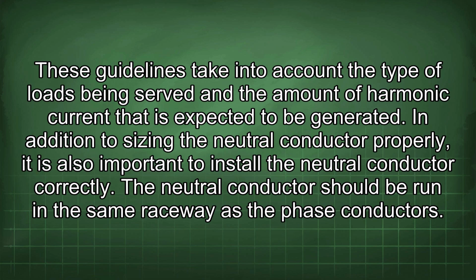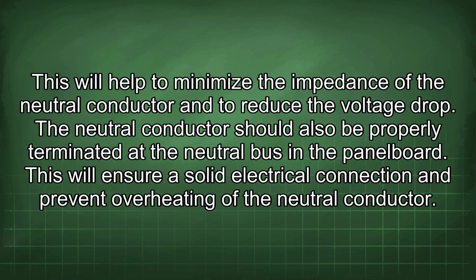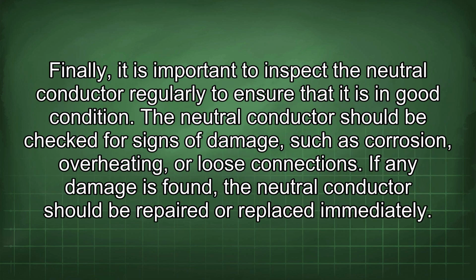In addition to sizing the neutral conductor properly, it is also important to install the neutral conductor correctly. The neutral conductor should be run in the same raceway as the phase conductors. This will help to minimize the impedance of the neutral conductor and to reduce the voltage drop. The neutral conductor should also be properly terminated at the neutral bus in the panel board. This will ensure a solid electrical connection and prevent overheating of the neutral conductor. Finally, it is important to inspect the neutral conductor regularly to ensure that it is in good condition. The neutral conductor should be checked for signs of damage such as corrosion, overheating, or loose connections. If any damage is found, the neutral conductor should be repaired or replaced immediately.